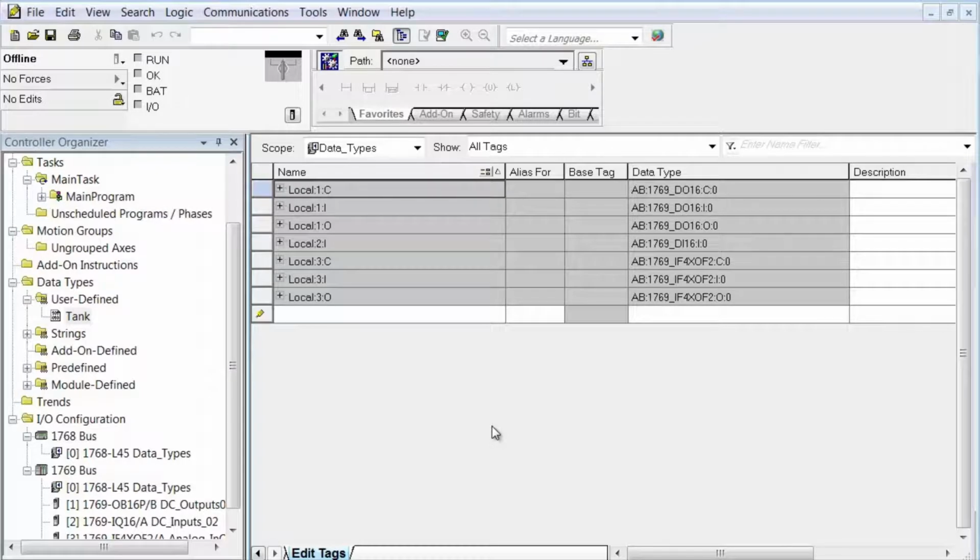So now, if we were to duplicate our example here of the data in Studio5000, you would have to describe and symbolize each member of your tank data, not once, but every single instance you added another tank to your logic. I've done this type of programming with PLC5s and Studio5000, so I know how tedious it is. Now, there are some shortcuts. You can export and import, you can index your addressing as you import, and you can do a lot of things to save time. But it's still a lot of work, and you've got to pay very close attention to what you're doing.